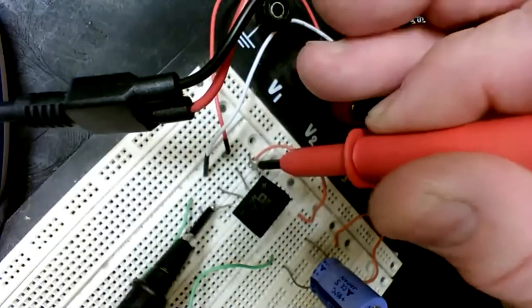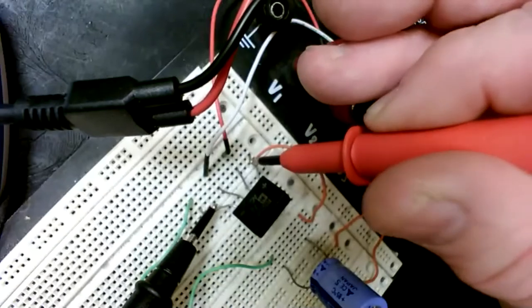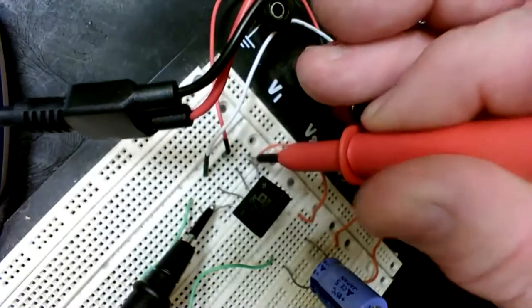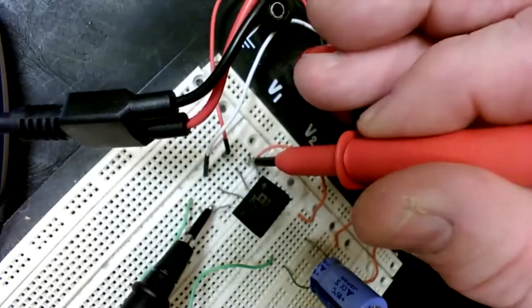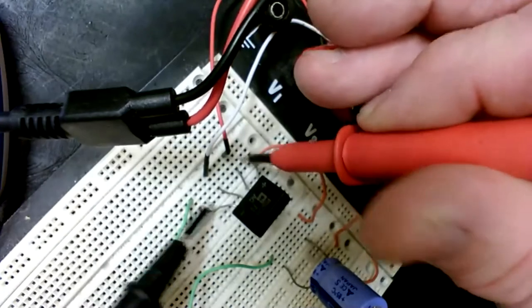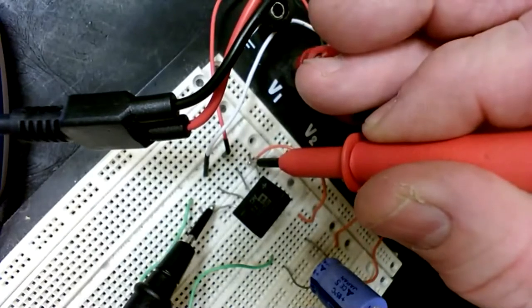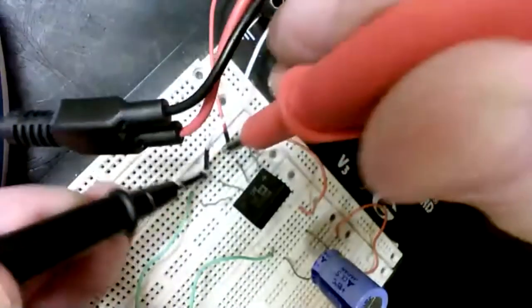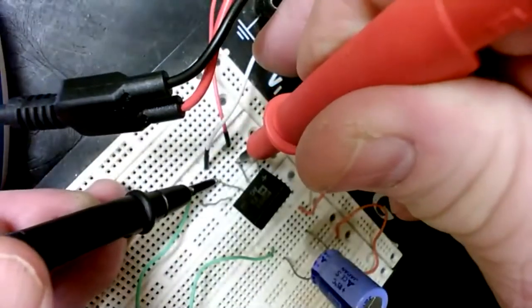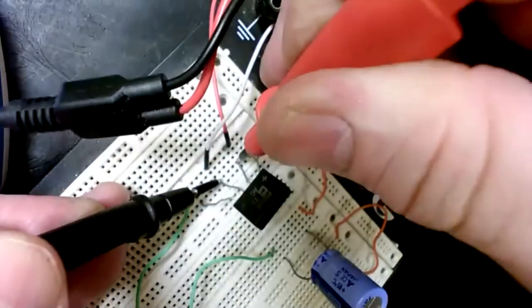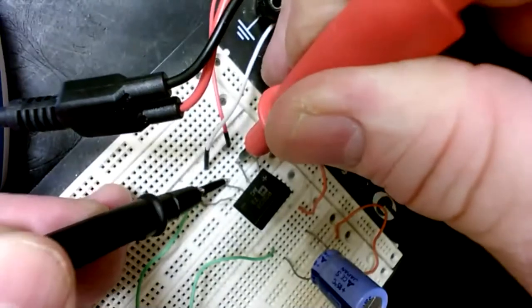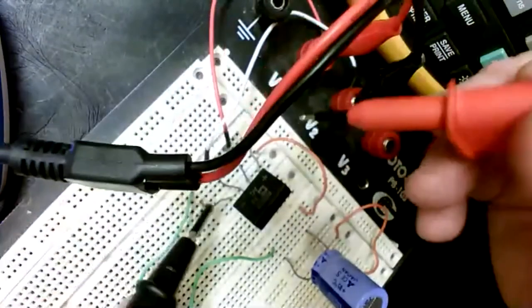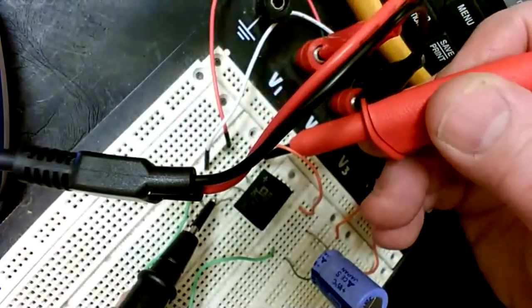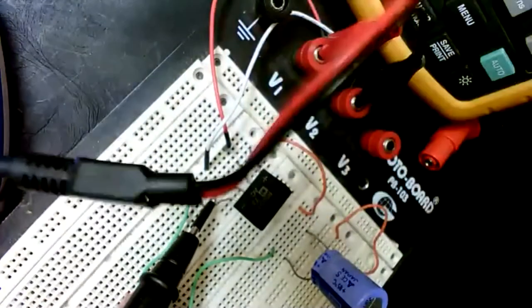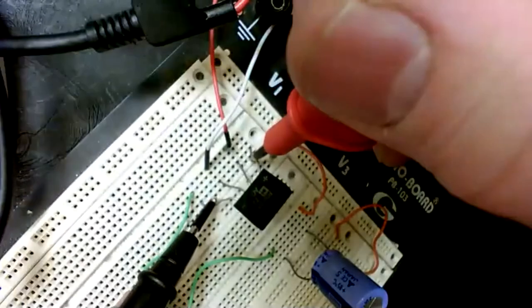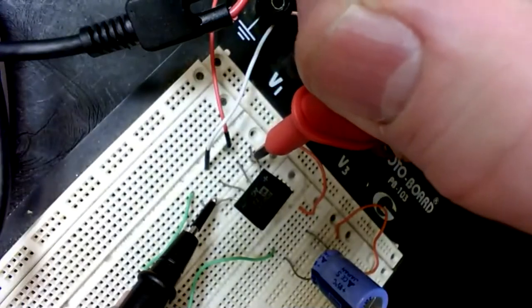When I go to the outside legs like that, I put the red on the positive lead and I put the black on the negative lead. I'm going straight to the output legs on that rectifier, and it's giving me those positive pulses. When I check the incoming, I go to the center legs here, like that. You see it? So I'm checking the incoming going there, and I'm checking the outgoing on the outside legs by moving those probes to those small leads there. Everybody sees that, right? Okay.